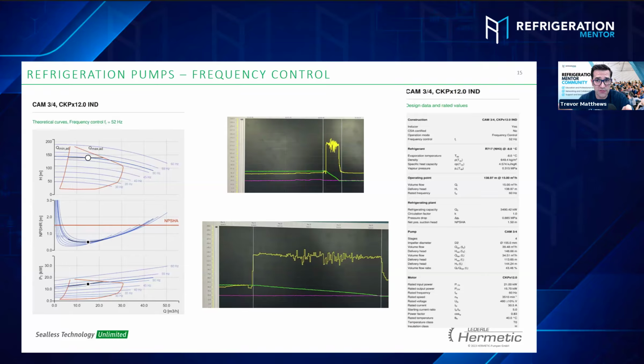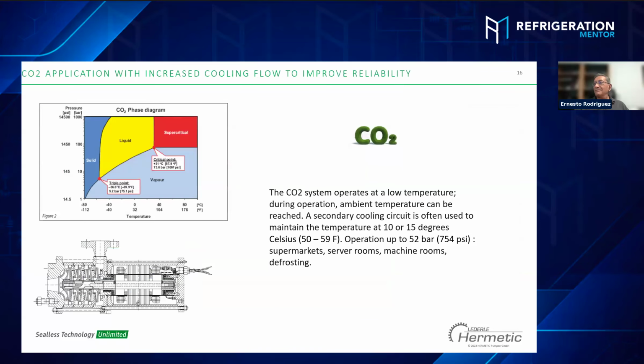And there are other ways to manage the flow in the system, right? Besides the drive. Correct. So if it's designed for 52 hertz and now we move that up to 55 hertz, now we have more hertz, more work on the motor, our amps will go up. Those amps start to cause heat, because we're generating more heat in the stator, and because the liquid cools the motor, that heat will start to flash the CO2. Is that what you're getting at? Perfect. Yes, correct. Flashing is the number one problem, and 90% of the problems with CO2 pumps are flashing. This is the reason I want to show this slide: be careful when using VFDs. It's an excellent device, but you need to be careful in your application.